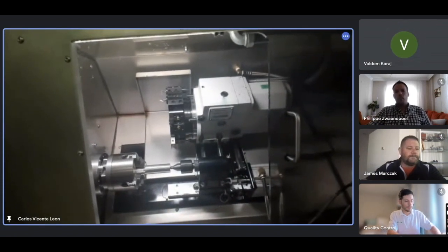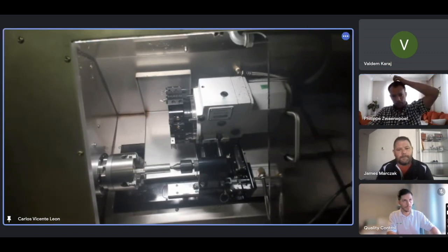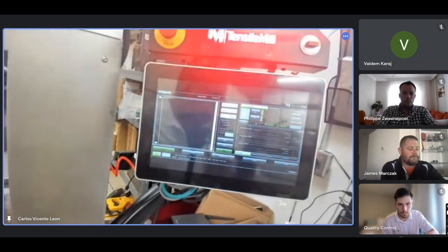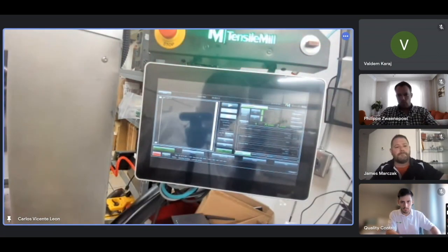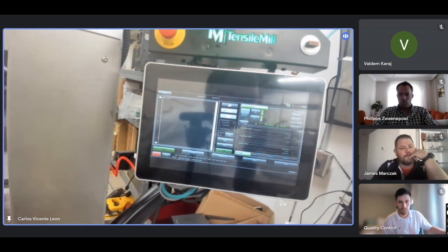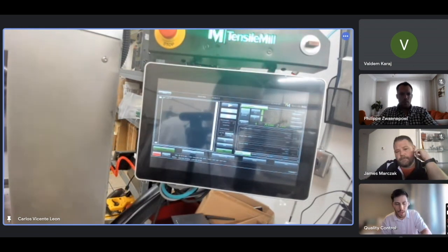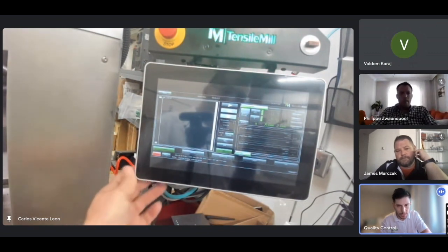Sometimes the tail stock might be too strong. Can you change the sensor to metric? You can. All these values here are in inches at the moment. The filter, the manometer, can be worked in bars. I'm going to send you the procedure. But the control at the moment is only inches. We have something actually in the works right now for bringing in the metrics, so we should be able to update the software remotely to bring that to them once it's on site.